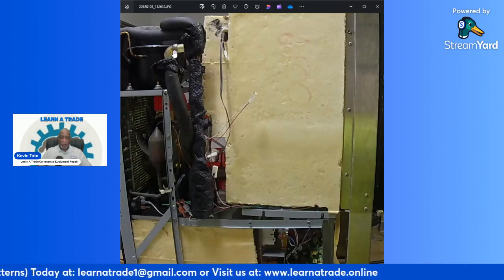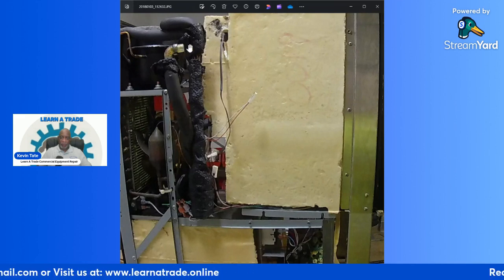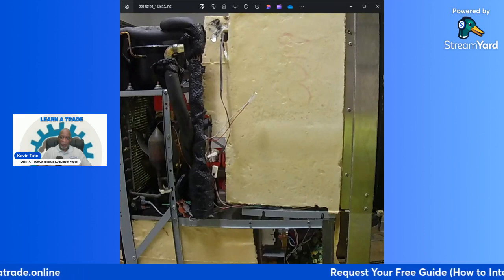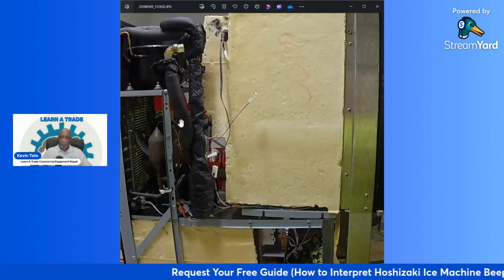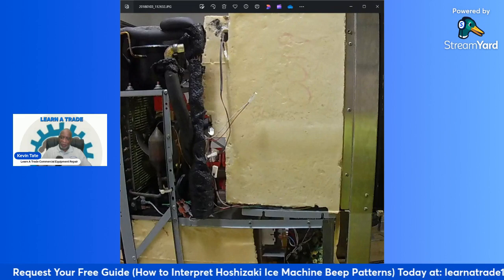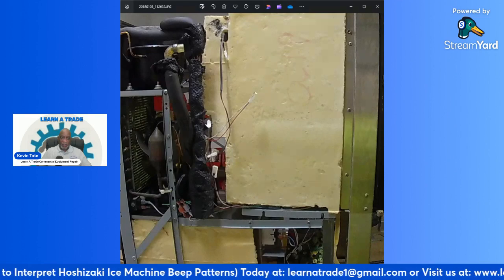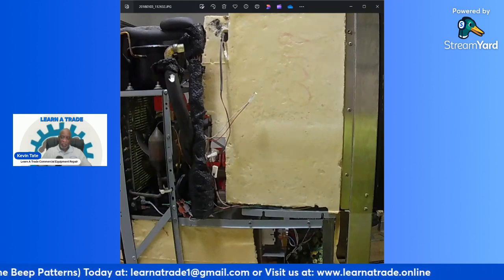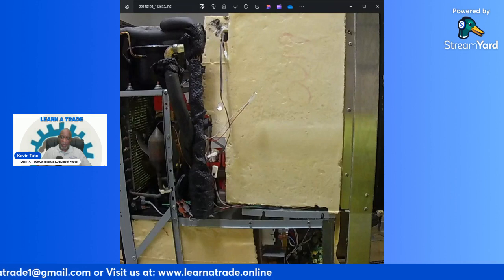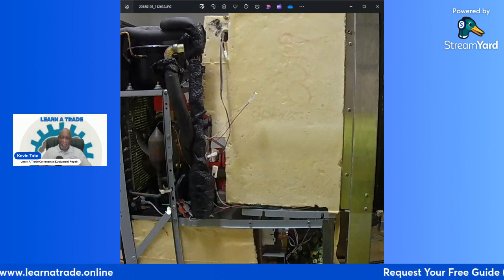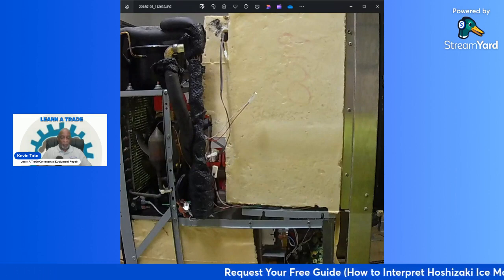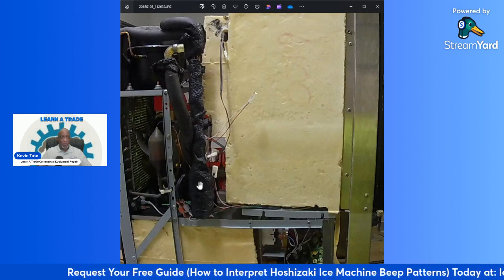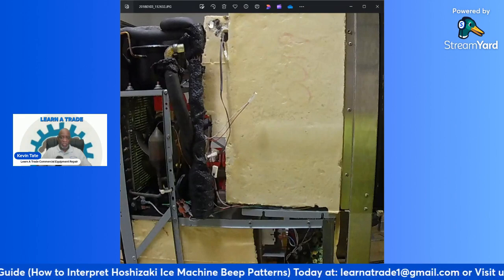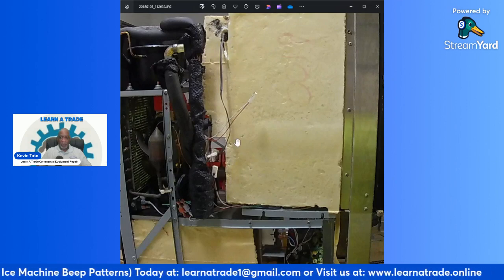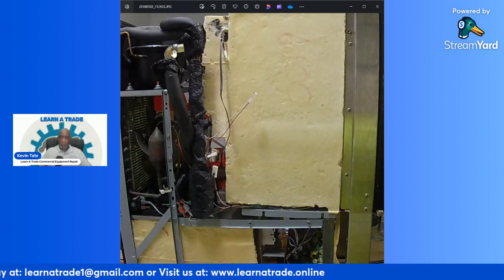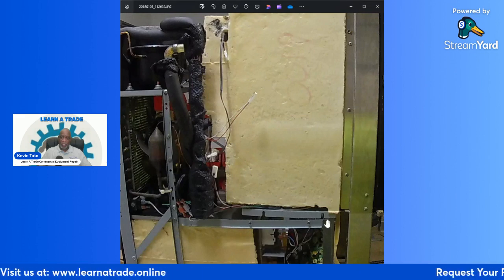There's an inlet hose for the cold water, where the cold water flows through the evaporator. This connects to the upper portion of the evaporator, and there's another tube connecting below on the lower end of the evaporator. So water comes up, runs through the evaporator, and comes out through the other tube back into the water bath. That circulate pump circulates the water over and over, continually sending cold water through the evaporator through these hoses. So those hoses also had to be disconnected in order to pull this cabinet off.